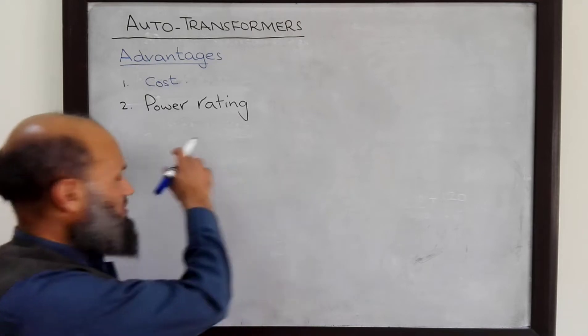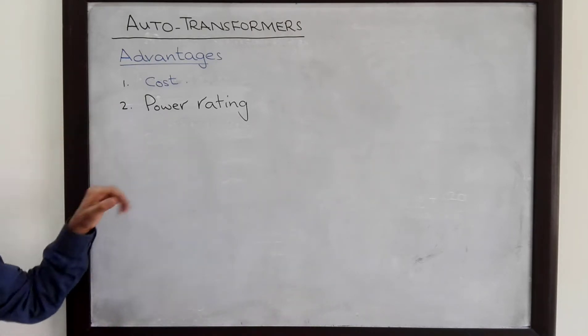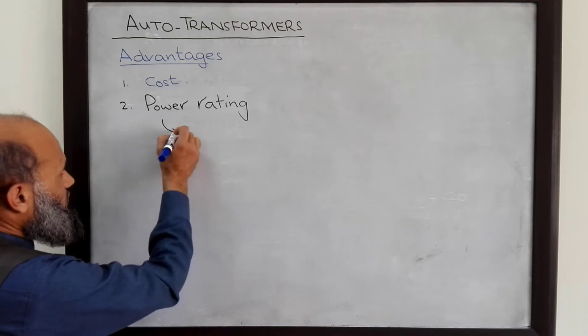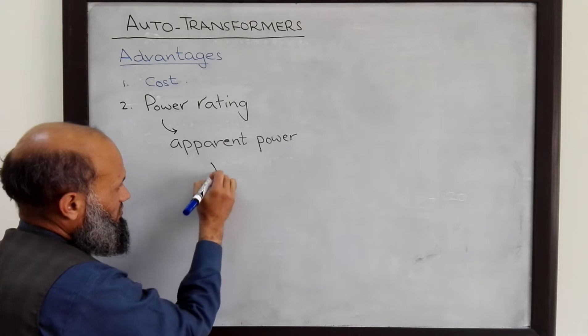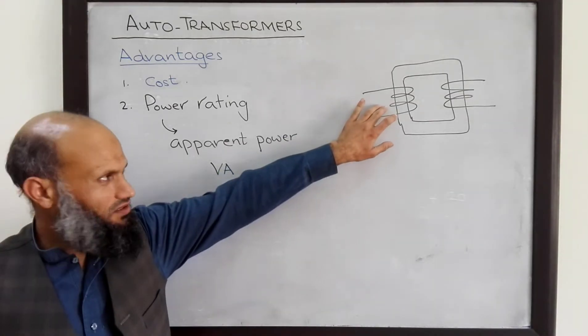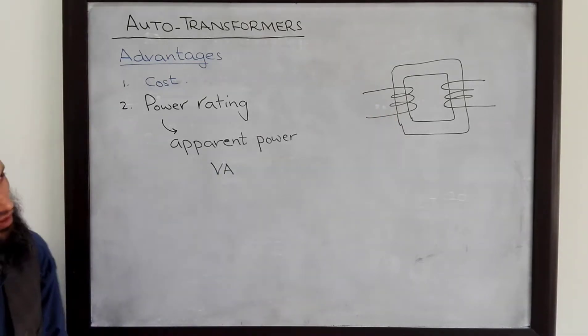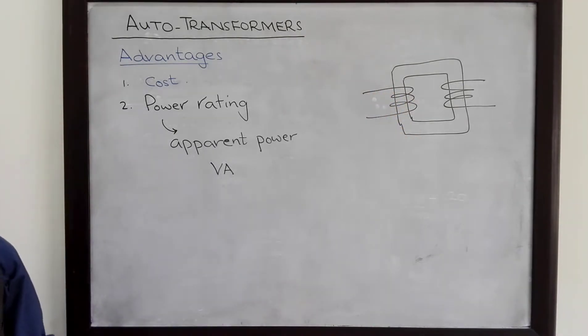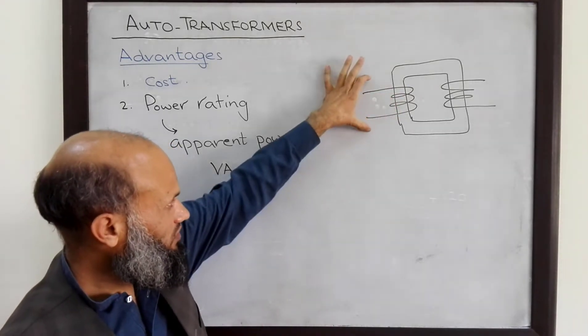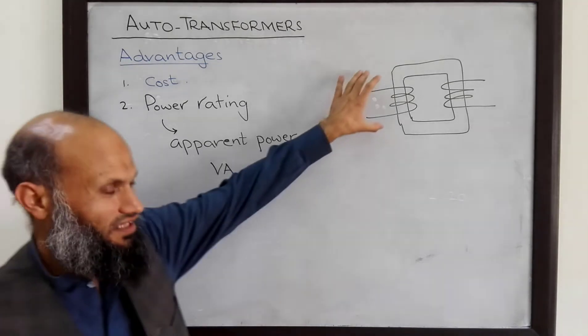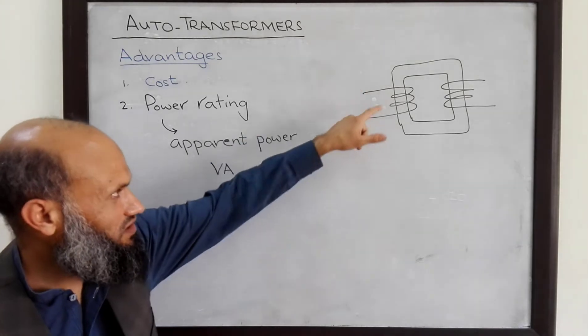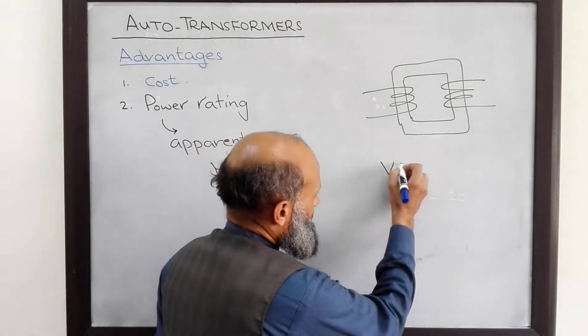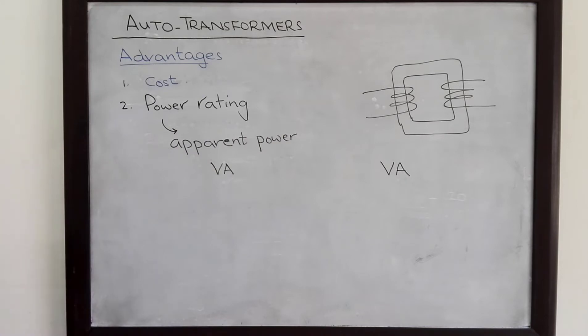The power ratings of electrical machines are always apparent power ratings — that is, the volt-ampere rating. The primary and secondary windings of transformers are made of copper; however, they still have some small resistance. When current flows in the windings, heating is produced, and therefore the maximum current the windings can handle is limited. Likewise, the maximum voltage that can be applied to the primary and secondary windings is limited, and therefore the apparent power rating is limited for a transformer.